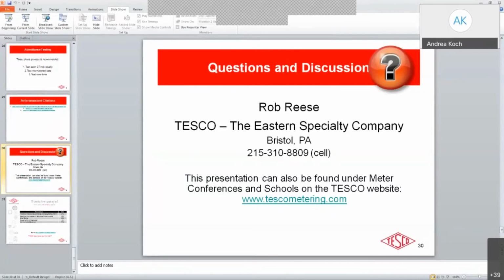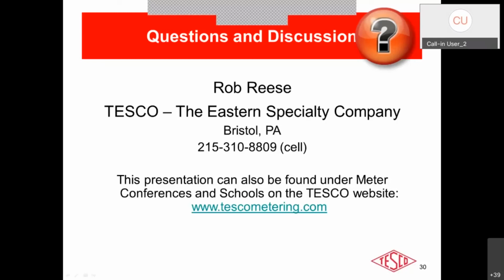So let's see. I think you may have answered this one earlier. When you get bad results from a burden or ratio test, what should I do? Yes, I covered that earlier. The main rule of thumb to keep in mind is the last thing you should look at is the CT itself. You will inadvertently find a ton of different issues other than a bad CT. So always look at that last, double check everything else, your wiring, your test switch, meter seating in the socket, etc.